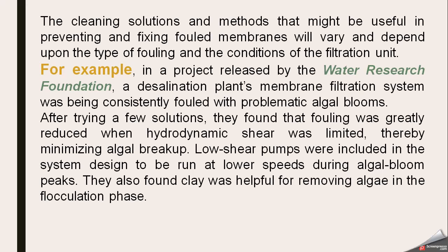So they tried different solutions and ultimately they found that fouling was greatly reduced when hydrodynamic shear was limited, thereby minimizing the algal breakup. So when they apply hydrodynamic shear or force, that will reduce or break the algal size, it increases the fouling. However, when they reduce this shear and minimize algal break, they found that this will reduce the fouling.